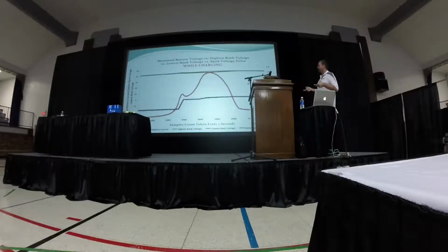And you can see what happens with the high and the low bank. This is our voltage delta right here. At the top of the curve, where the EVCON did turn off completely, our bank delta was about 1.6 volts between the highest bank and the lowest bank. At the bulk state of charge, we were down here, and I remember the test, it was 0.2 volts, so 200 millivolts between the highest and the lowest bank.